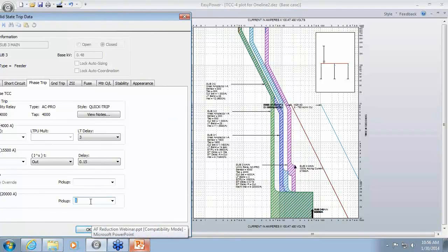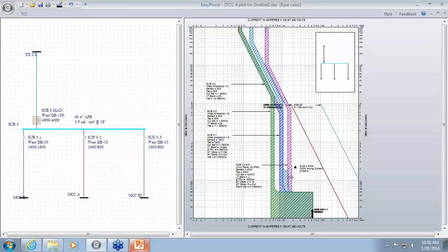Still not quite there, so go down to 4. Okay, so by implementing the maintenance mode, and it has an instantaneous, it's down here, it's covered by the other devices, but it'll reduce it to 3.9 calories. So this is just to say that sometimes, even though you put in a device that has a maintenance mode setting, the risk of people not putting it back to the normal state may not be at that level.